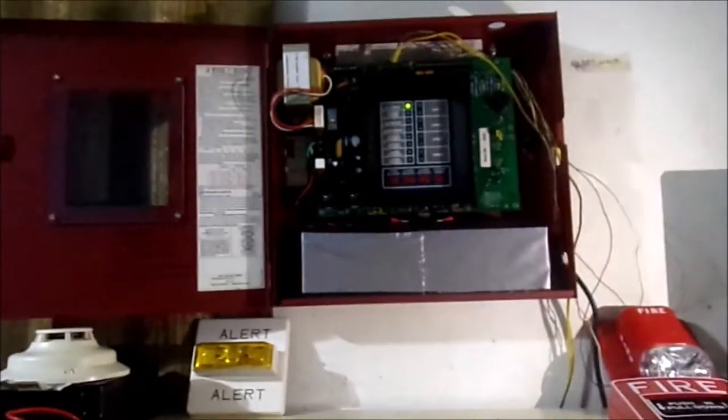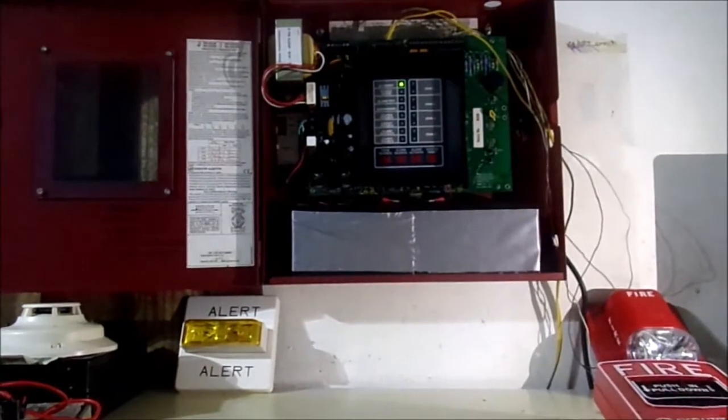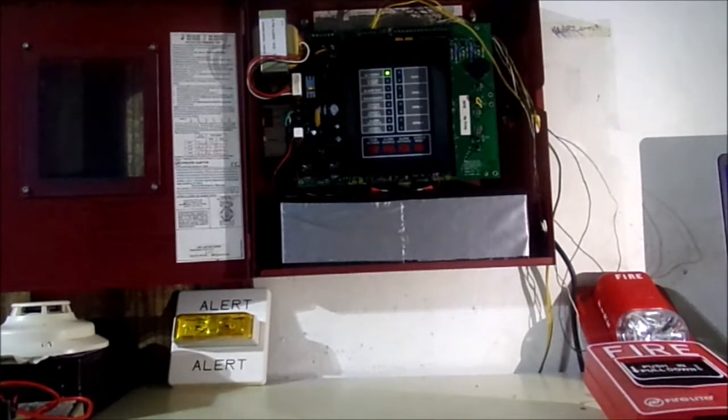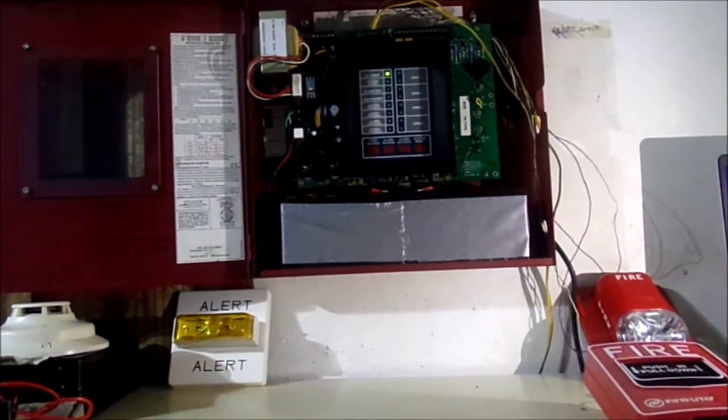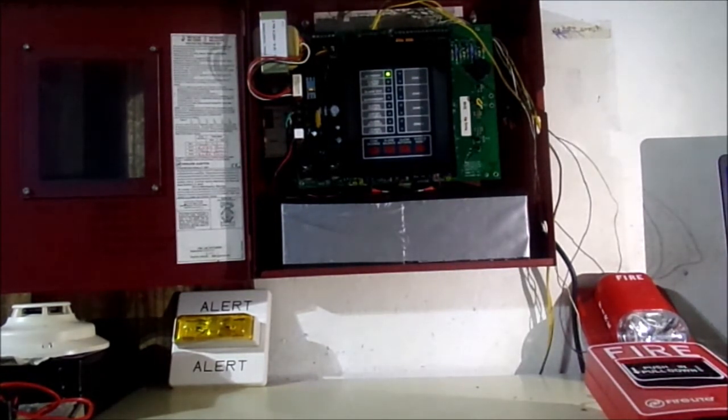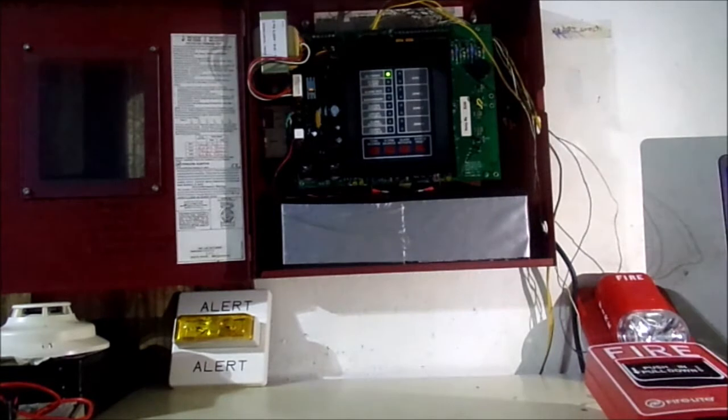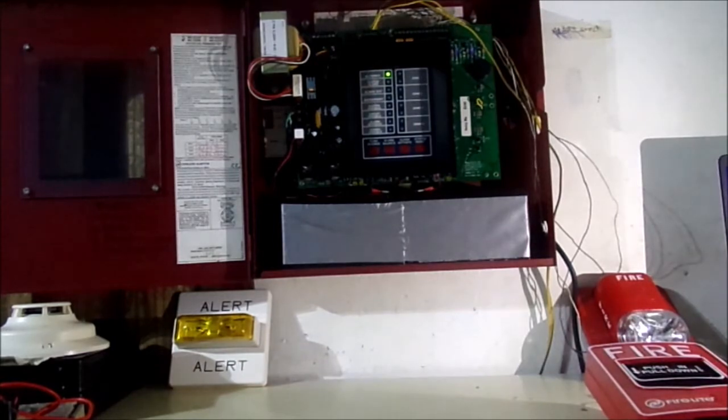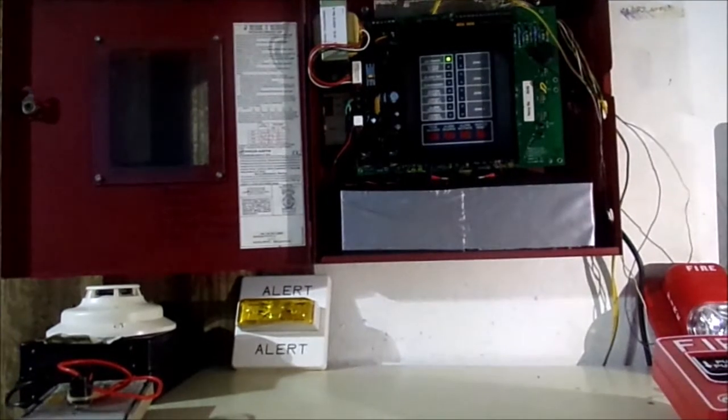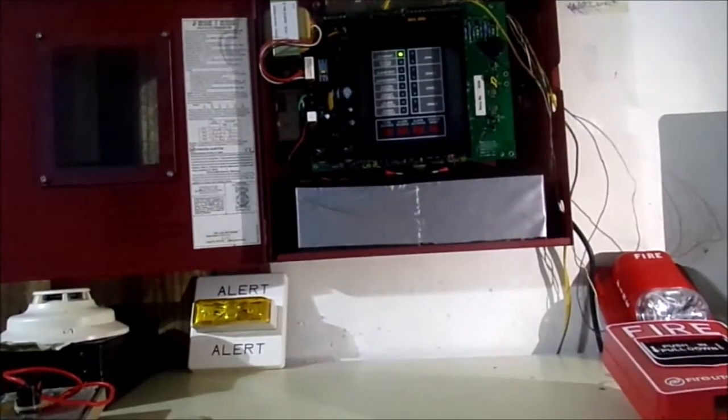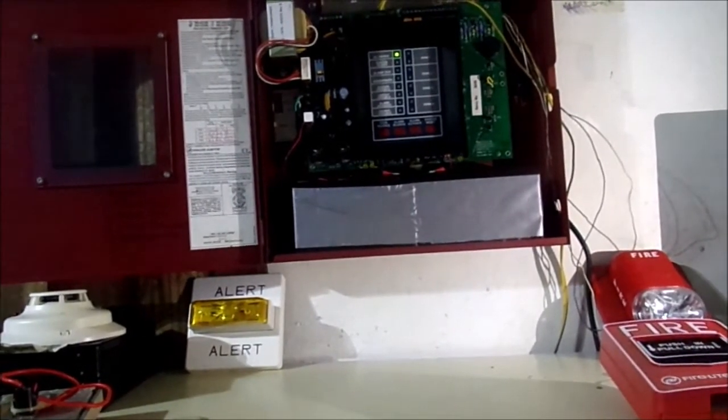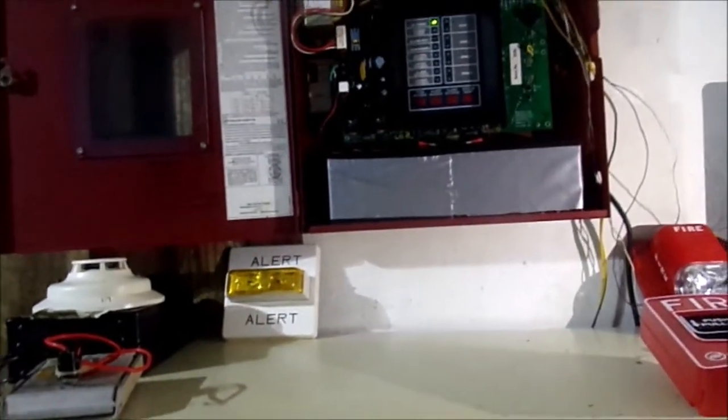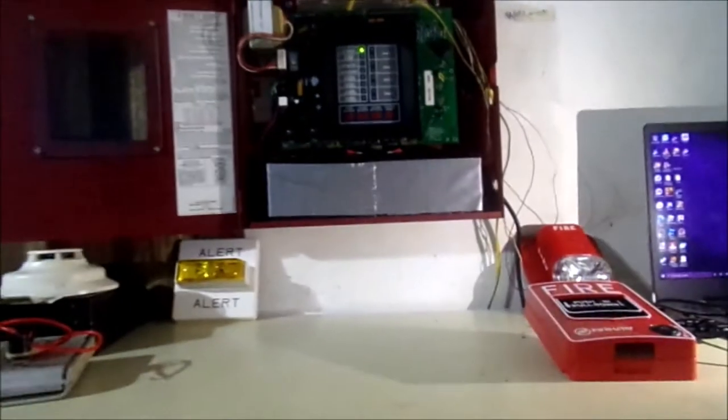Besides the point, I want to indicate one thing. This fire alarm control panel, if it's plugged in, is output FWR. Which means full wave rectified. So, what that means is that instead of DC or AC, it outputs FWR. Some fire alarms are not designed to handle FWR. And you have to check the back of these devices or the manual inspection of each product. Both of these can handle FWR, which is why I'm using them right now. And another thing, if you want to use DC or something like that, what you got to do is disconnect the fire alarm from a power source and only use battery. The thing is, you're going to get in trouble each time you reset the system. The best thing you can get is probably another fire alarm control panel that can do filtered DC. Besides that, we're going to test this.